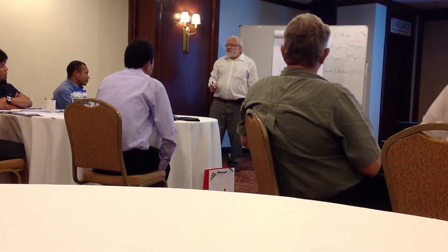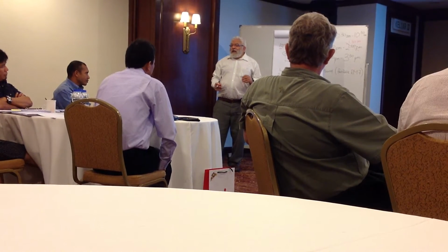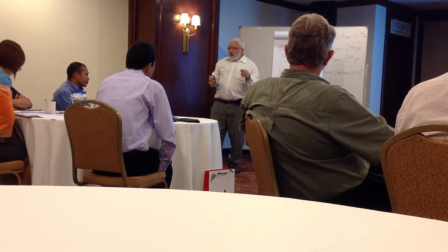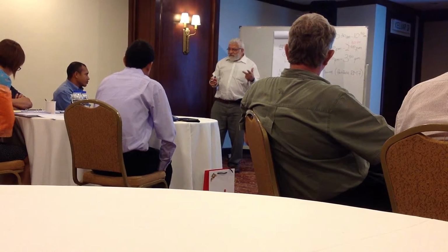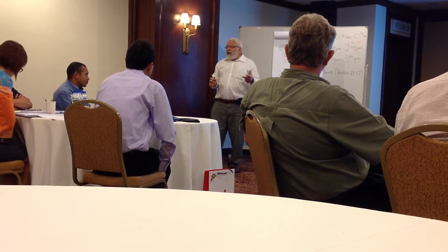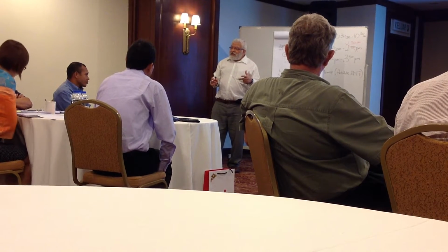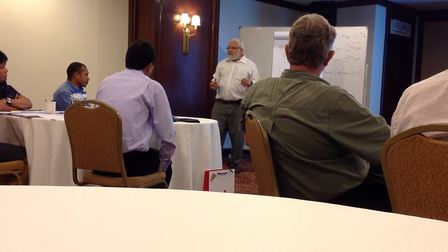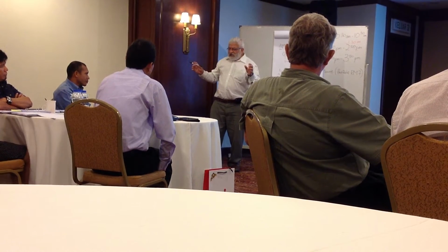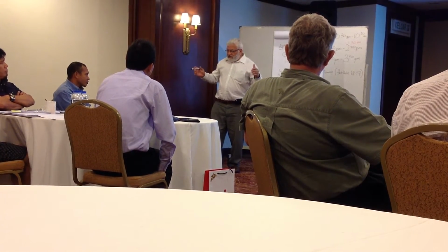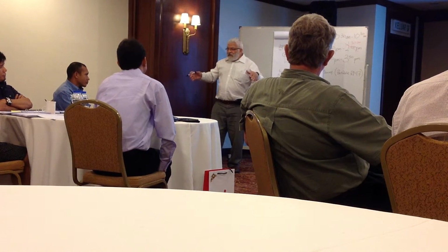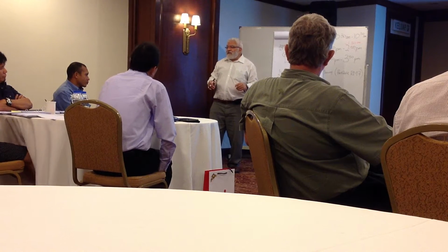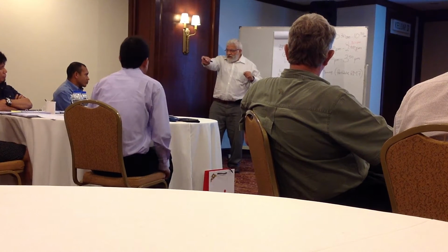Now he says, if I look at the voltage drop on phase A and phase B and for phase C, I will find that the voltage drop is not the same. The two guys on the outside will have a drop that's identical to each other, but the fellow in the middle has a different voltage drop, linear, okay?